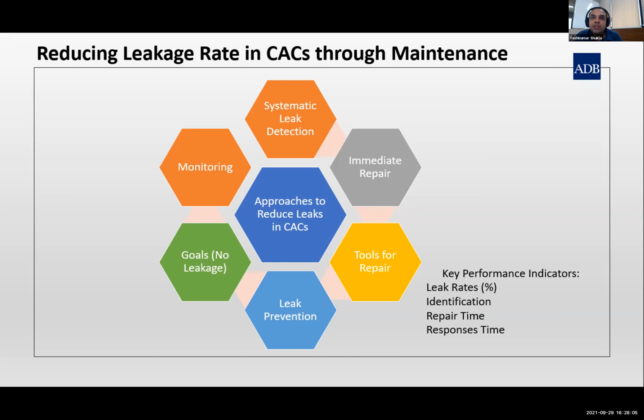Some of the key performance indicators that are often used are, first, leak rate: the percentage of refrigerant leaked in a year compared to the total refrigerant installed in a facility. Then the identification: how quickly and how the leak was identified. The repair time, how quickly it was repaired, and the response time. These are the metrics you can have in your maintenance system to reduce the leakage rate. And finally, you do performance monitoring to verify that the strategies you have are actually working for the site.